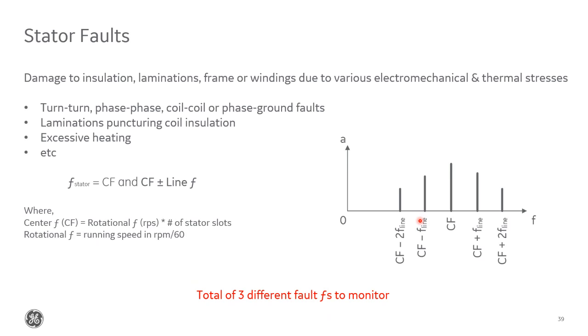For the newer firmware, this is the only calculation that we need to do. We're looking at 3 different frequencies. In the older firmware, we have an additional calculation to this that incorporates this one in addition to the rotational frequency sidebands. So we used to look at 6 different fault frequencies. But again, since we've shifted the input signal we're analyzing, now we only need to take into account the stator's center frequency and the line frequency sidebands of it.